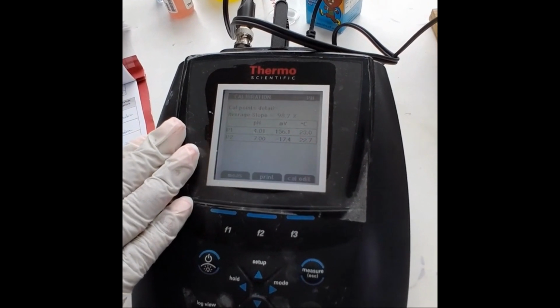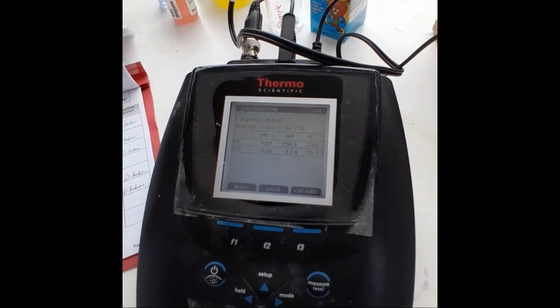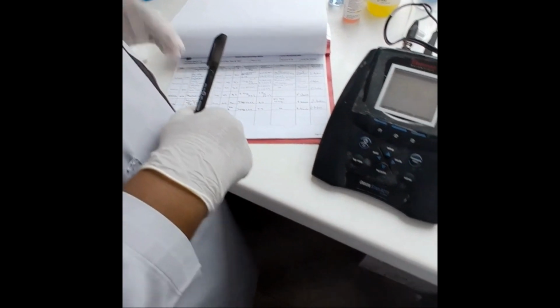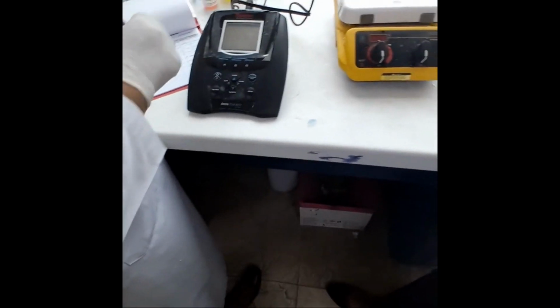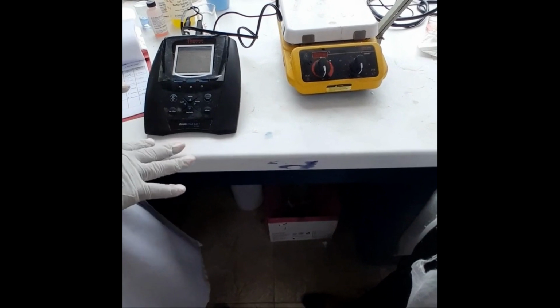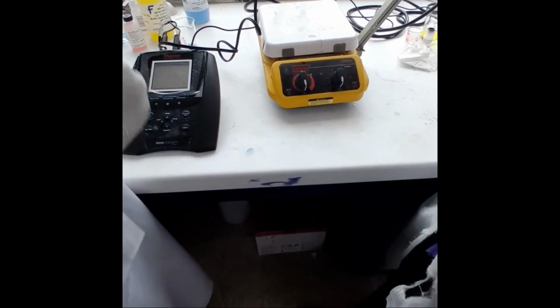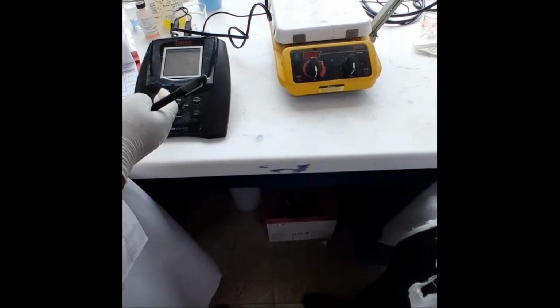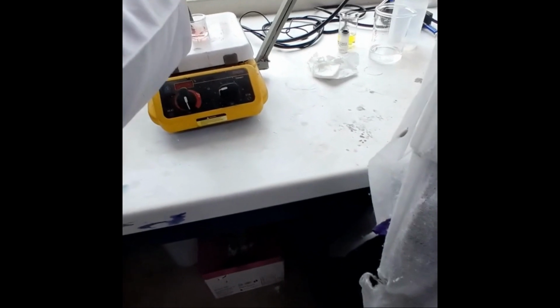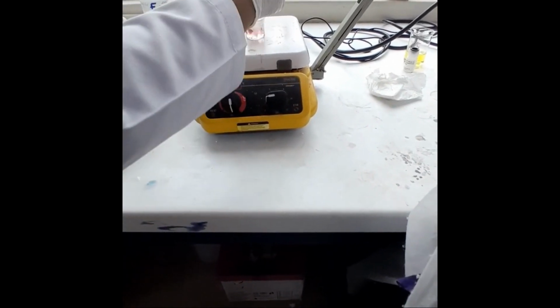So now we get our slope. The slope is 98.7. The acceptance limit for the slope is 92 to 102. If we have done the calibration and the slope falls outside that range, we have to recalibrate or change our buffers. The next step would be to measure buffer 4. Since we have calibrated, what we want to find out now is what buffer 4 reads based on the calibration. We'll just put the probe back in it, since it was the last one.